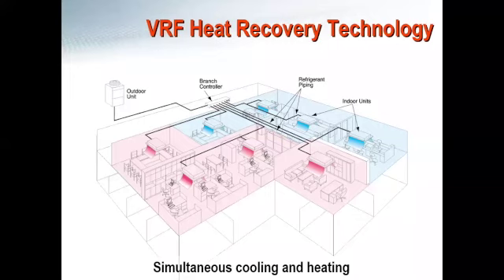So what it allows us to do is move energy from zones in cooling to zones in heating without using the outdoor unit. It's important to realize, and I don't know if this is something that everyone knows about, so I'm going to touch on it quickly, that when you're cooling a zone, you're not necessarily providing cooling to that space, you're removing heat. So when that refrigerant goes into your zone in cooling, it's absorbing all of the heat in that space, and typically you'd send it out to your condensing unit, and all of that energy would be dispersed into the atmosphere. What the BC controller does is it allows us to take all of that waste energy from zones in cooling and divert it as hot refrigerant over to zones in heating. We call it free heat or energy recovery in this instance.